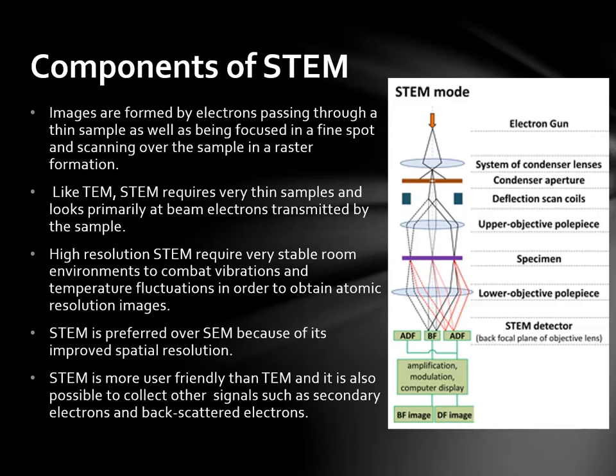Images are formed by electrons passing through a thin sample as well as being focused in a fine spot and scanning over the sample in a raster formation. Like TEM, STEM requires very thin samples and looks primarily at beam electrons transmitted by the sample. High-resolution STEM requires very stable room environments to combat vibrations and temperature fluctuations in order to obtain atomic resolution imaging. STEM is preferred over SEM because of its improved spatial resolution, and it is more user-friendly. It is also possible to collect other signals such as secondary and backscattered electrons.